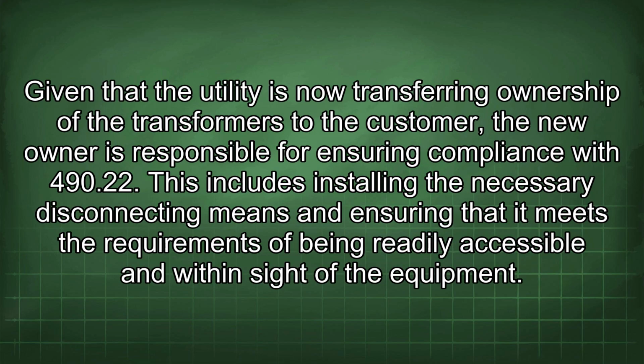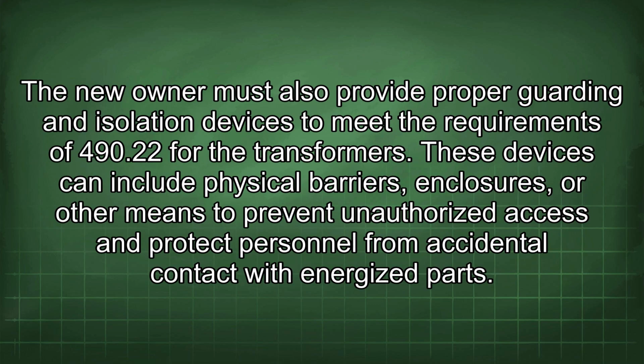an emergency. Given that the utility is now transferring ownership of the transformers to the customer, the new owner is responsible for ensuring compliance with 490.22. This includes installing the necessary disconnecting means and ensuring that it meets the requirements of being readily accessible and within sight of the equipment. The new owner must also provide proper guarding and isolation devices to meet the requirements of 490.22 for the transformers. These devices can include physical barriers, enclosures, or other means to prevent unauthorized access and protect personnel from accidental contact with energized parts.